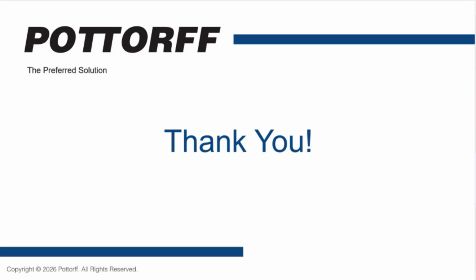And I think there's one of our competitors that has a pretty good document on it. They did a lot of the internal lab testing, and we all kind of use those same numbers. But from what I remember, just to be careful, you want to use at least a 20% add for a bird screen. It is a good add.